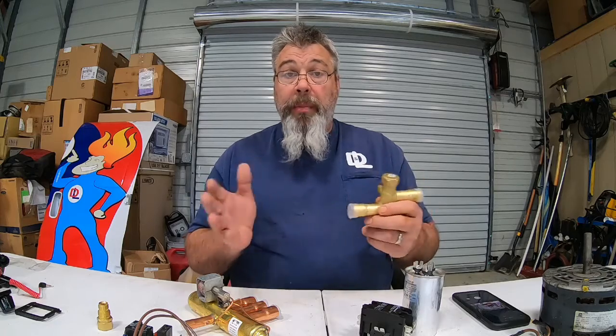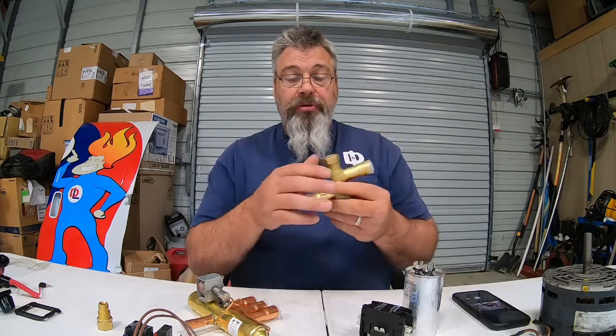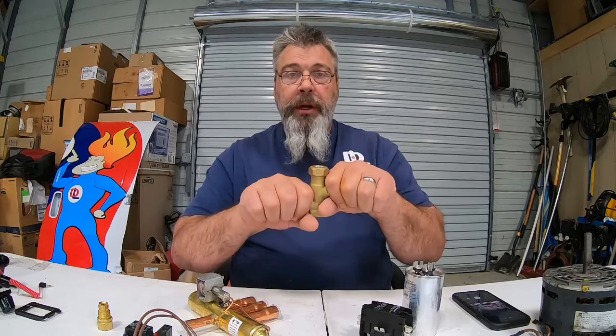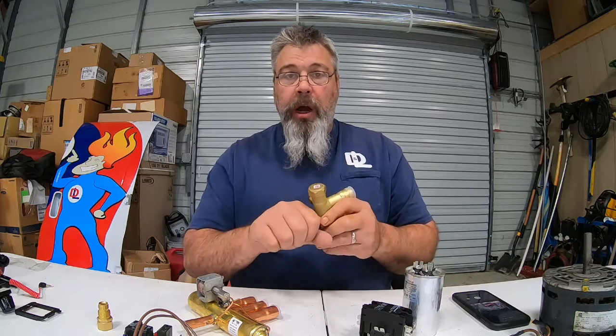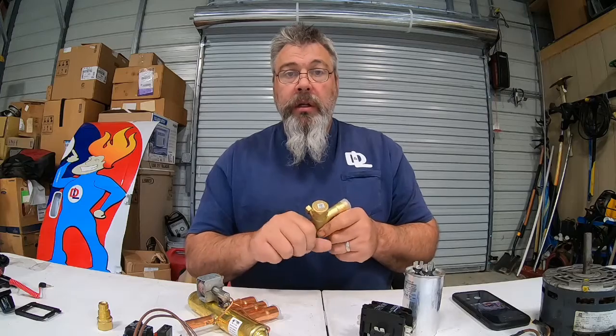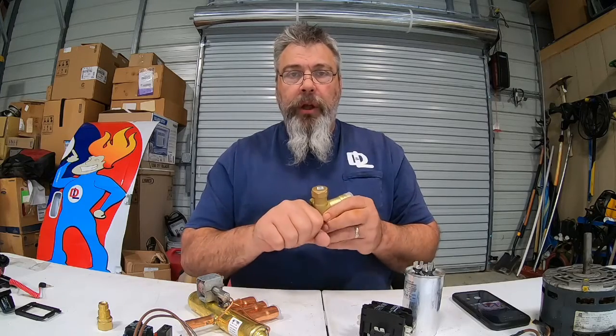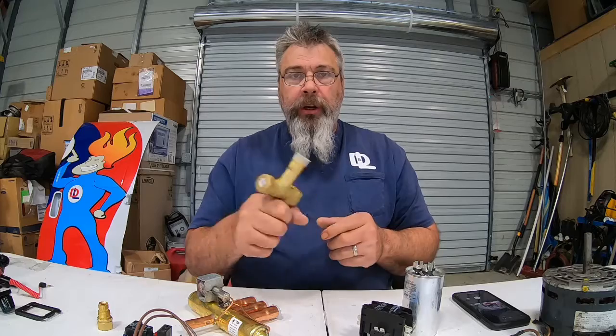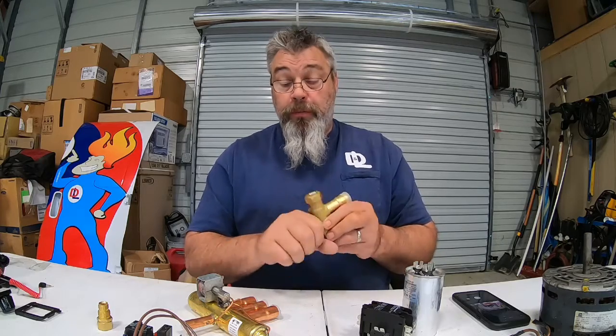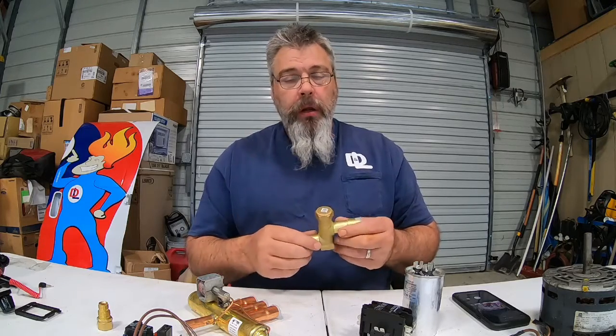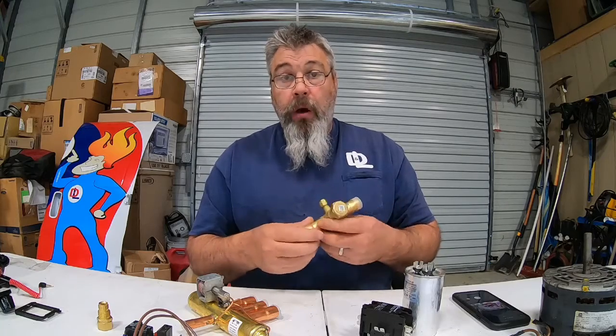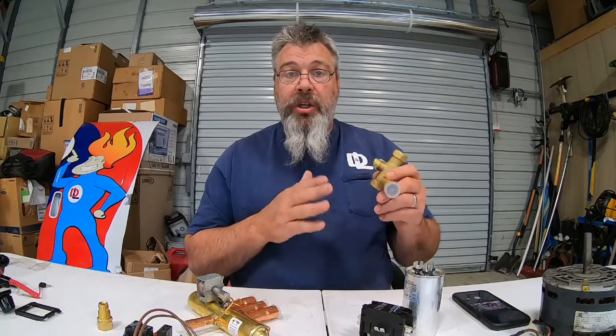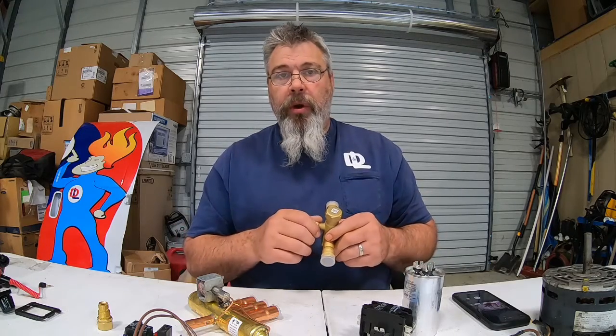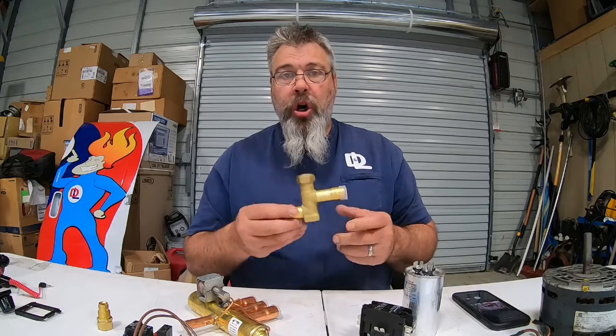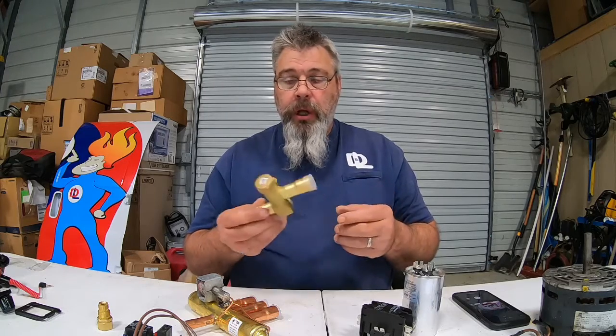So we talked about heat pump and AC. In straight AC mode, this will be ice cold in the summertime. The old timers back in the day when I first started here would say, check that suction line. Feel it. I said, okay, what does it feel like? Beer can cold. That's what they used to refer to. If it was bear can cold, the charge was good. We don't do that anymore. Manufacturers now require us to check it by subcooling or superheat. I'll do another video on subcooling and superheat to make sure your charge is proper on your heat pumps and your AC units.